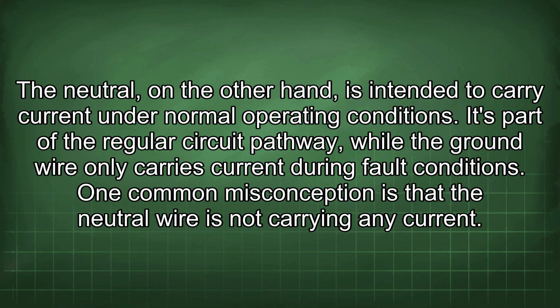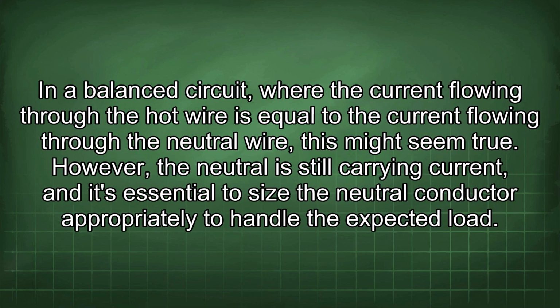The neutral, on the other hand, is intended to carry current under normal operating conditions. It's part of the regular circuit pathway, while the ground wire only carries current during fault conditions. One common misconception is that the neutral wire is not carrying any current. In a balanced circuit, where the current flowing through the hot wire is equal to the current flowing through the neutral wire, this might seem true.